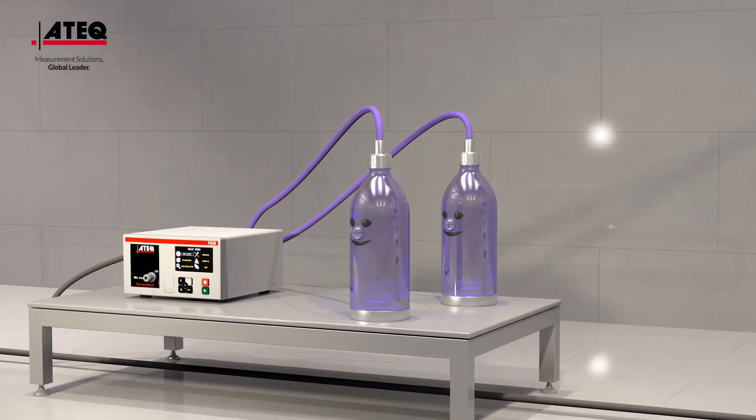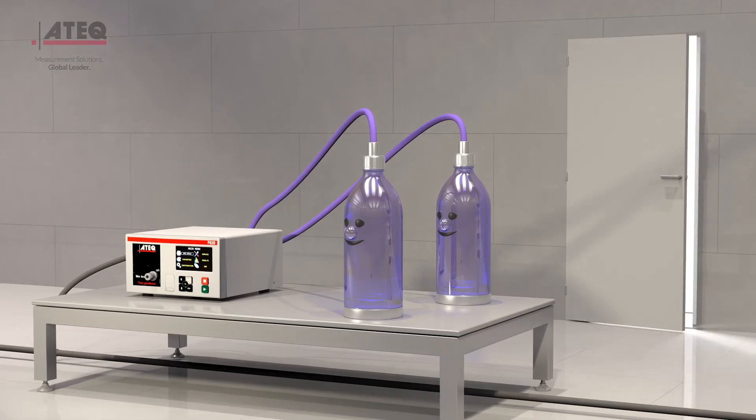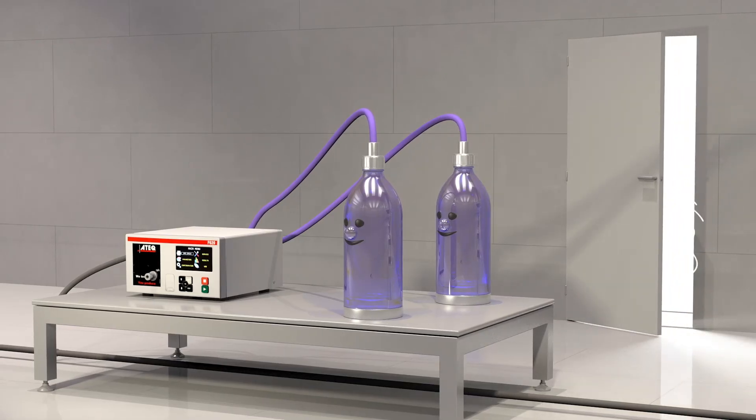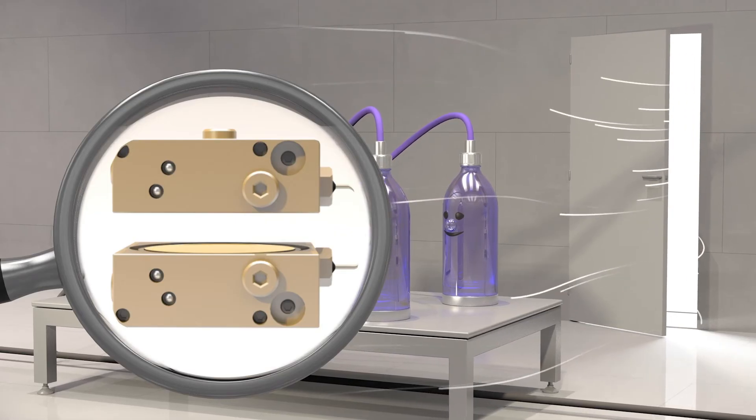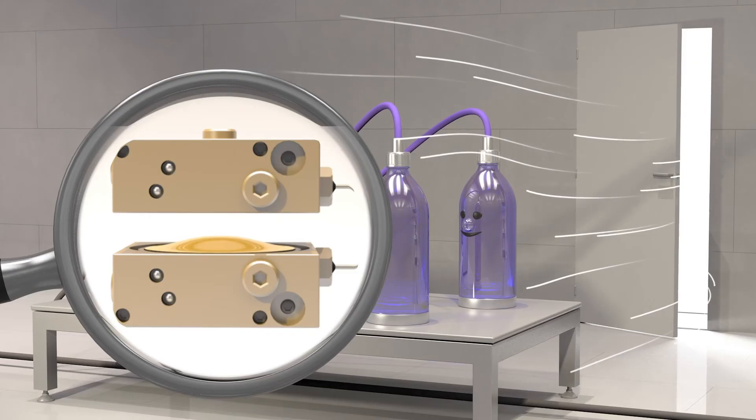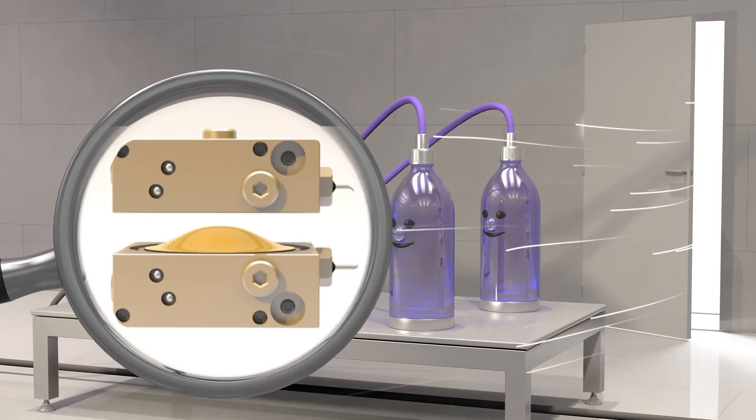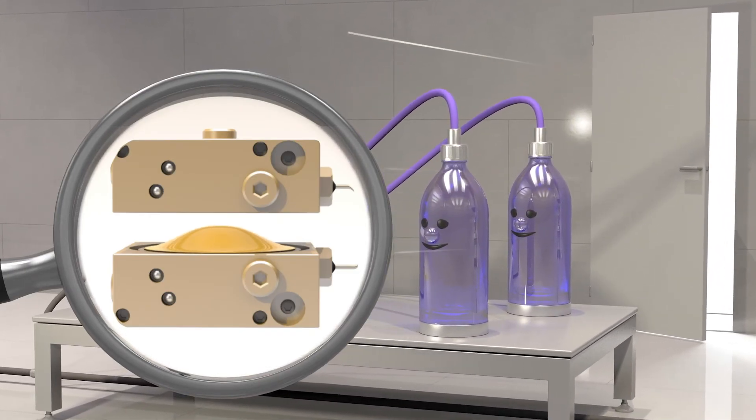But the differential pressure drop has another benefit. When ambient disturbances such as air currents occur, the differential pressure test is not affected. The micropressure variations resulting won't occur on the two pieces at the same time and in the same proportions. Only a leak will create a difference and will be detected.